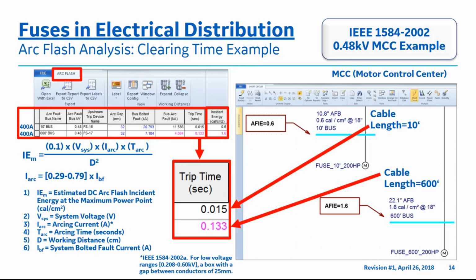From the arc flash report highlighted in red at the upper left-hand side of the screen, notice that the trip time window that is enlarged and shown in the center of this slide shows the 10-foot cable with a 400 amp fuse with a clearing time of 0.015 seconds, and the 600-foot cable that has the same upstream 400 amp fuse clearing at a different time interval of 0.133 seconds, which is just under 10 times longer to clear. This represents the arcing time, or T-arc, in line item number 4 in the equation, which is an input to the arc flash incident energy equation on the upper left-hand corner. The arcing current clearing time requirement is the standard in the 2017 NEC 240.67 code, as the paragraph specifies 0.07 seconds or less for fuses 1200 amps or higher.